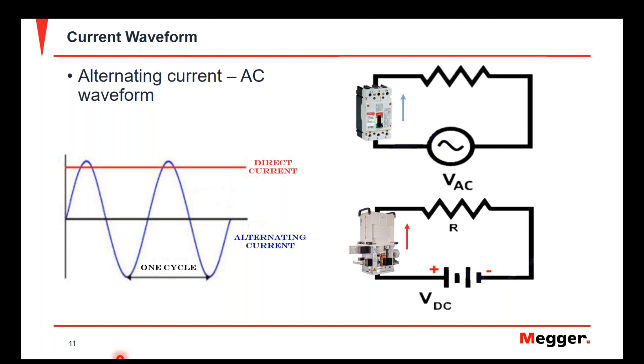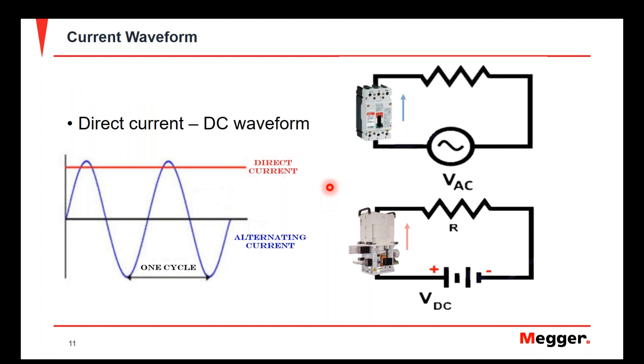Different circuit breakers require different waveforms, and we have different instruments that provide different outputs to satisfy these requirements. Typically for AC waveform, we use a typical molded-case circuit breaker with an AC current source to push current through and perform the primary current injection test. Another method uses a DC waveform for certain types of circuit breakers, such as a high-speed DC circuit breaker used in railway infrastructure or DC vehicular applications.